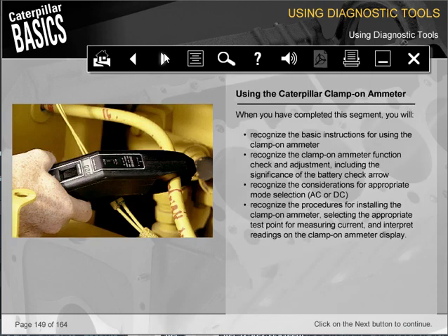When you have completed this segment, you will recognize the basic instructions for using the clamp-on ammeter. Recognize the clamp-on ammeter function check and adjustment, including the significance of the battery check arrow. Recognize the considerations for appropriate mode selection, AC or DC. Recognize the procedures for installing the clamp-on ammeter, selecting the appropriate test point for measuring current, and interpret readings on the clamp-on ammeter display.